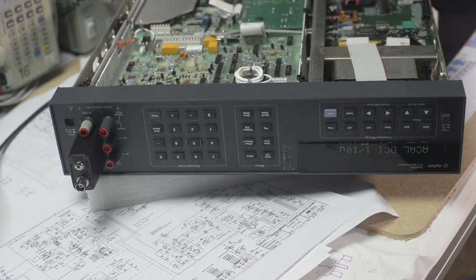Unrelated question: successful ACAL means short-term stability and parameters are within spec, not sufficient to conclude there aren't long-term stability issues, right? No, wrong. Successful ACAL means that the ACAL function works. So the meter is able to do the transfers internally, but all it needs to pass that is a couple of minutes of stability. It does not mean that the meter is stable, and it does not mean that the meter will actually meet the specifications. For all that, you still need to spend weeks and often months of testing and careful external calibration.